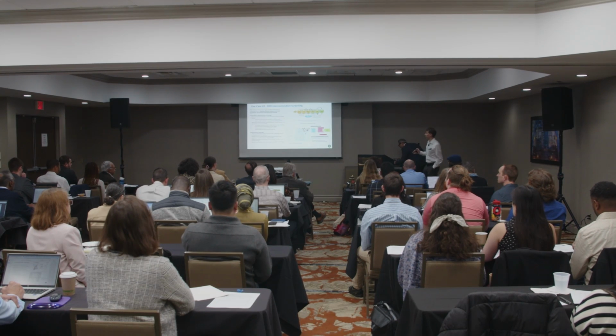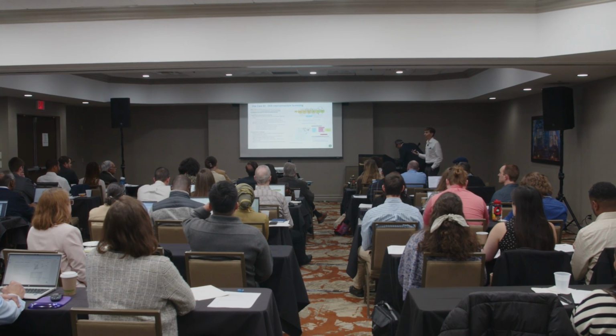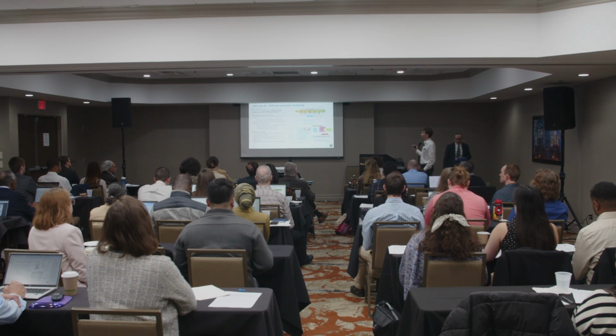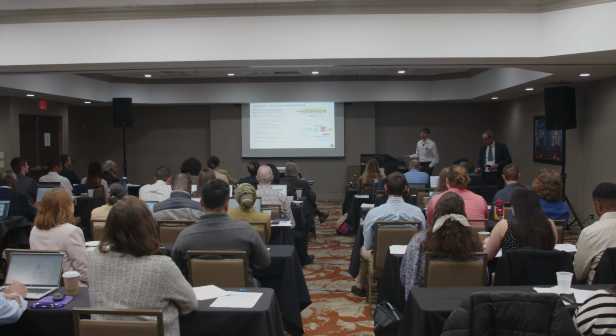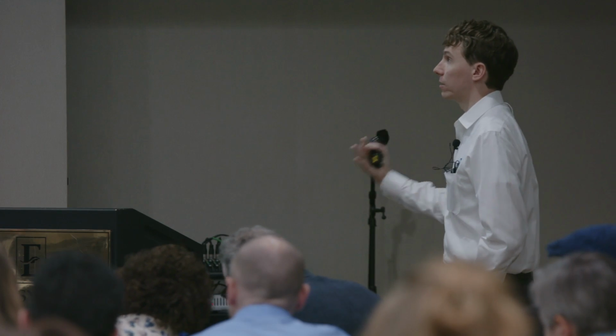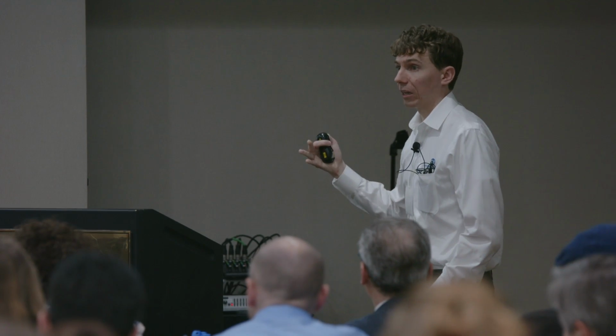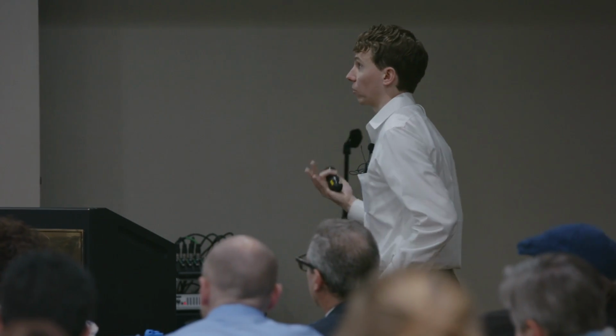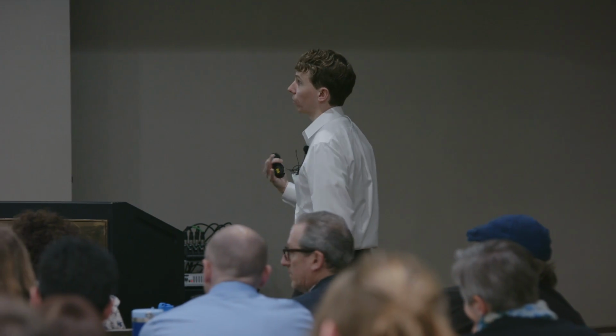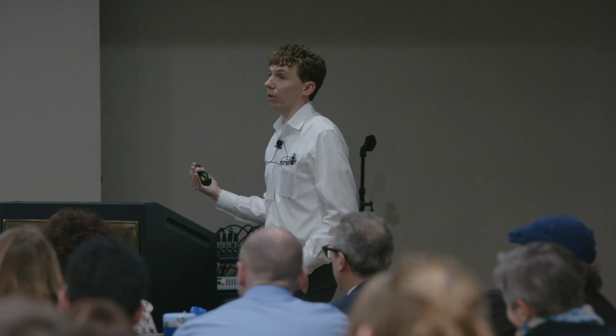Another use case is in the interconnection screening process. Knowing your limits can help you design better screens to accommodate new interconnections without having to run studies or do more detailed analysis. If you know you've got 5 megawatts of capacity on a feeder and you get an application for 100 kW, you know you're probably not going to have a limit. Designing a better process around this is a really useful way to build off of it.